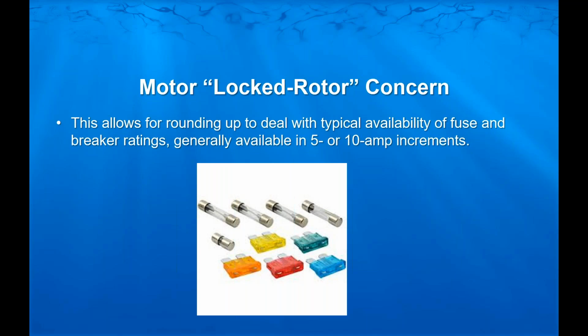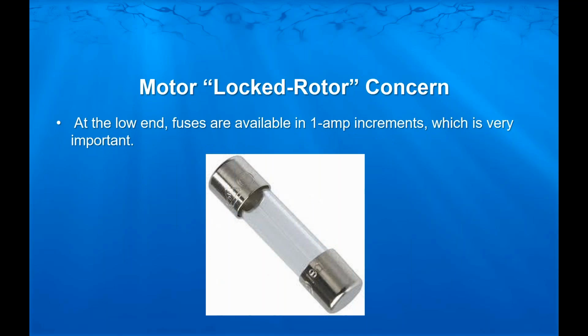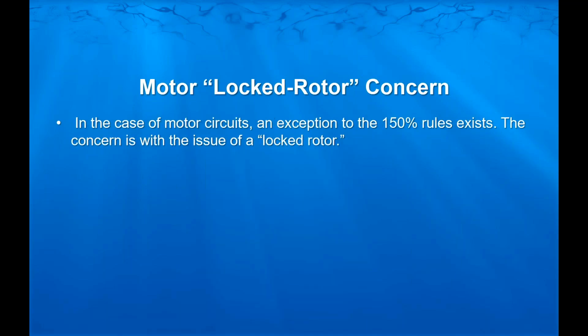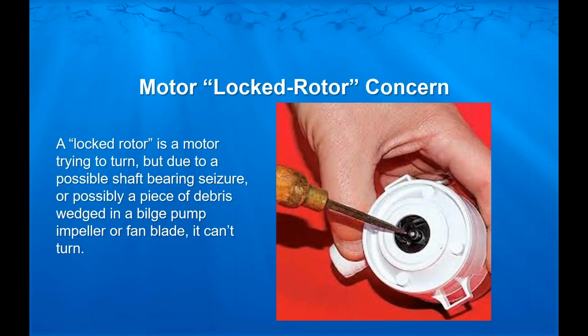The reason we allow that 150% of the rating of the wire is to allow for rounding up of overcurrent protection devices, fuses and breaker ratings, which are generally available in 5 and 10 amp increments. And the higher you get, the further apart the increments are. At the low end, where we're talking about here, fuses are available in 1 amp increments and even less, which is very important. In the case of a motor circuit, an exception to that 150% rule exists, and it's because of this concern known as locked rotor. A locked rotor is a motor that's trying to turn, but due to a shaft bearing seizure, a piece of debris wedged in a bilge pump impeller or a fan blade, the motor can't turn.